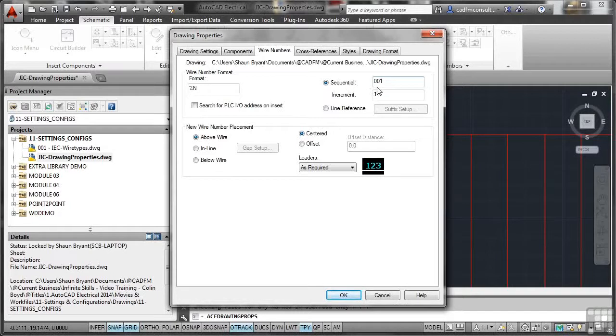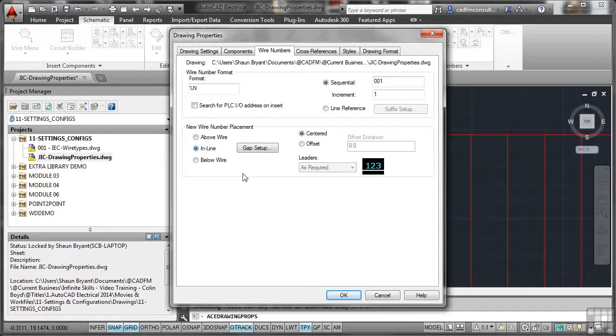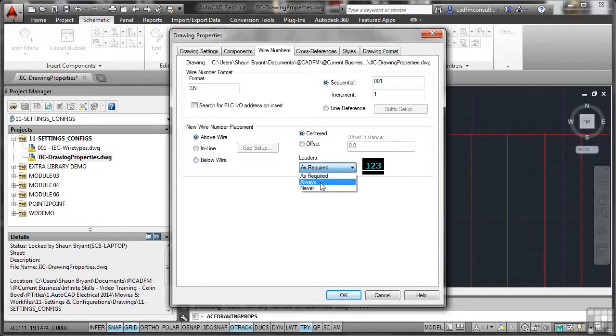A good project practice for wire numbering: normally you'd go for a sequential start of 010 and set the increment to 10 as well, because you never know when you need to add extra wires into a particular part of a project. You can also place the wire number above the wire, in line with the wire, or below the wire — I normally go above. You can have the wire number centered or offset, specify the offset distance, and set leaders to as required, always, or never. I just go 'as required' and let AutoCAD Electrical make that decision.